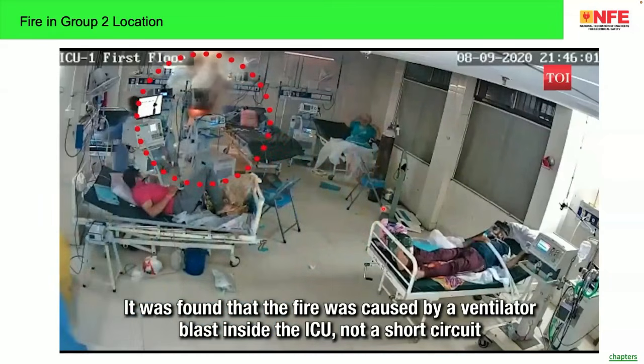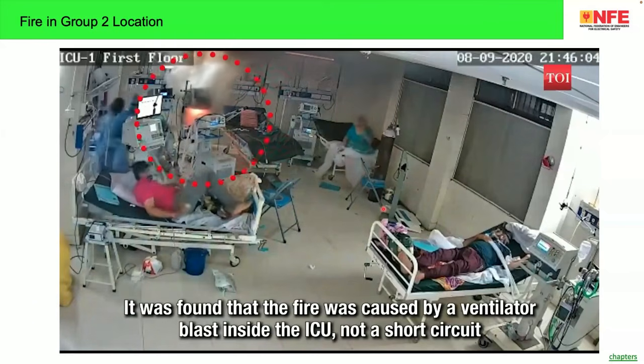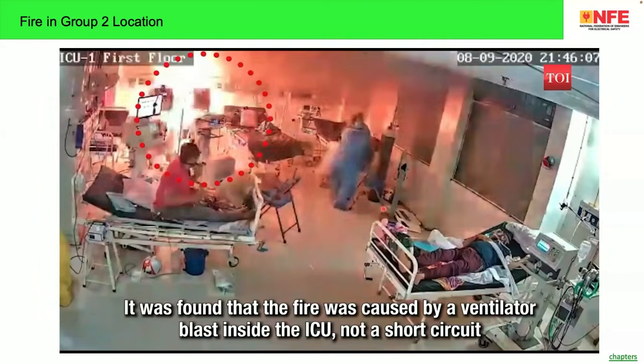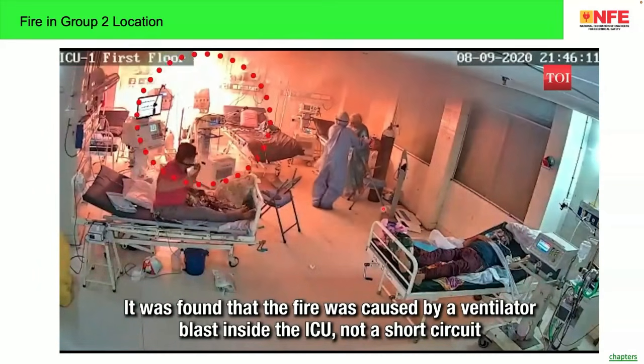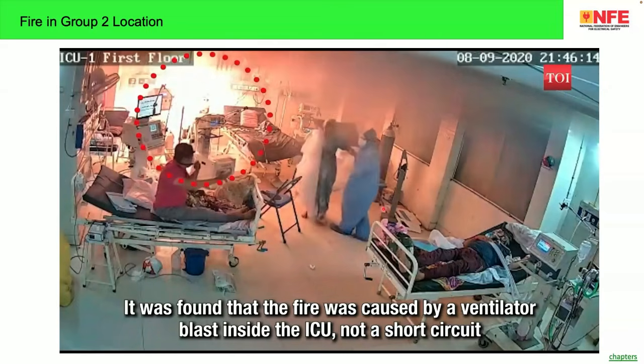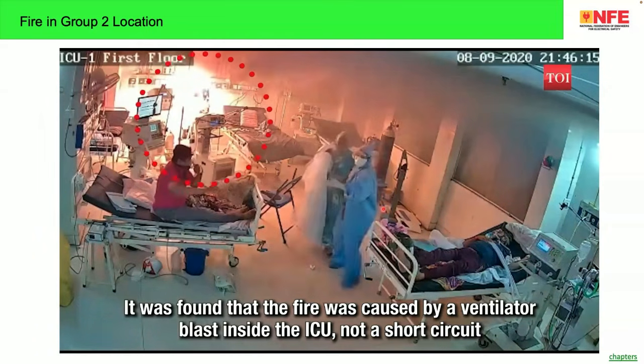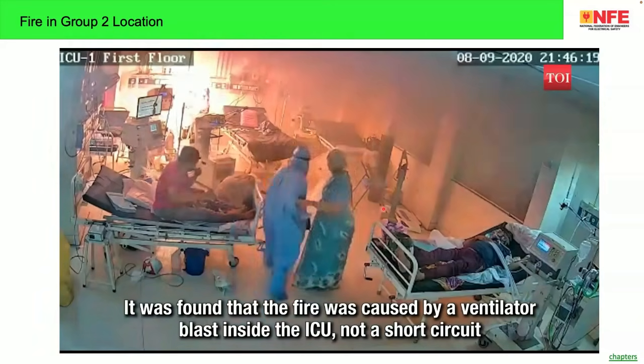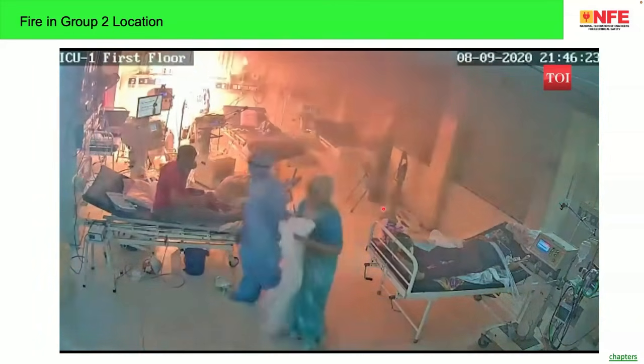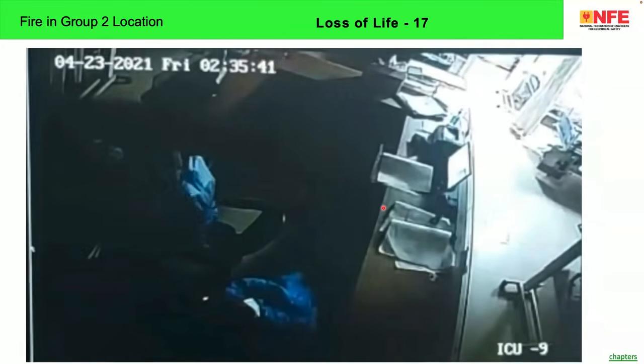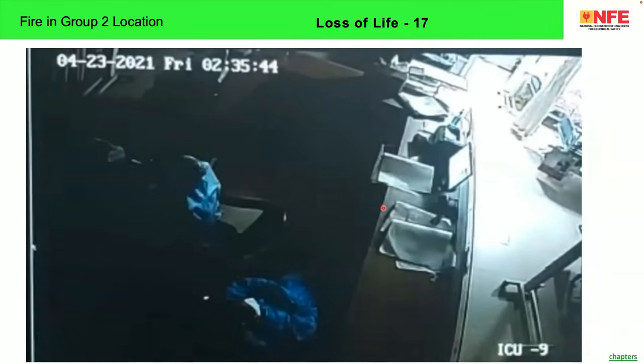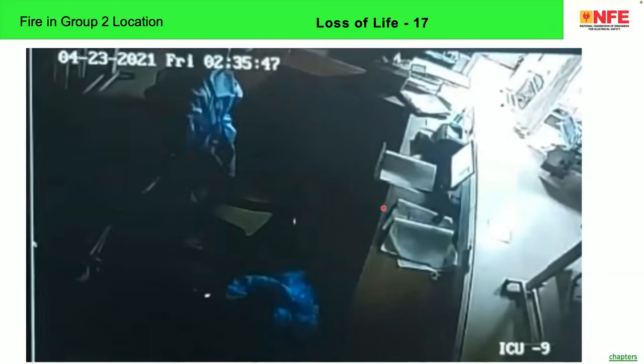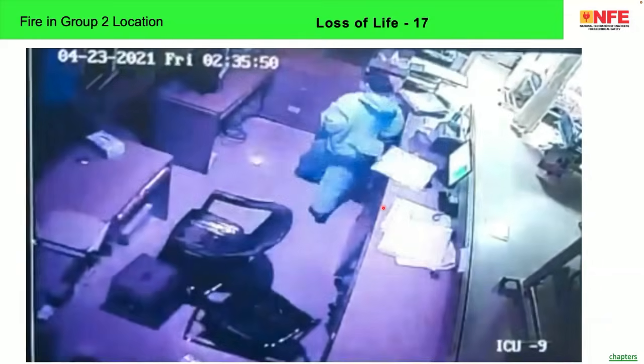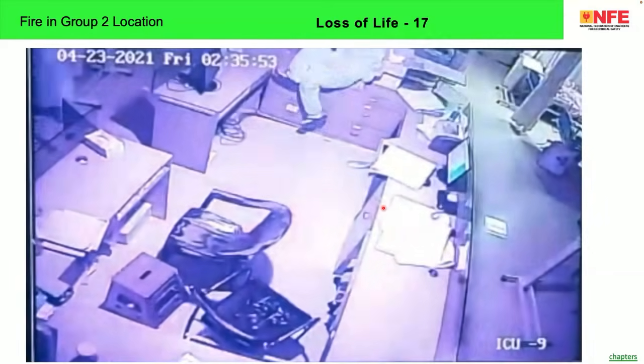Please note, biomedical equipment is supposed to work reliably even under a single fault condition. As I said, if your installation, your wiring, your protective device, or your sources like DG are unable to support the biomedical equipment in a safe way, of course, you will be in trouble. So fires like this can very much happen. Also, this is another case. 17 people died in this particular case. This is the famous Virar fire accident. One air conditioner, 17 people lost their lives. So sometimes we feel that the lives of the patients are not being taken seriously into account.